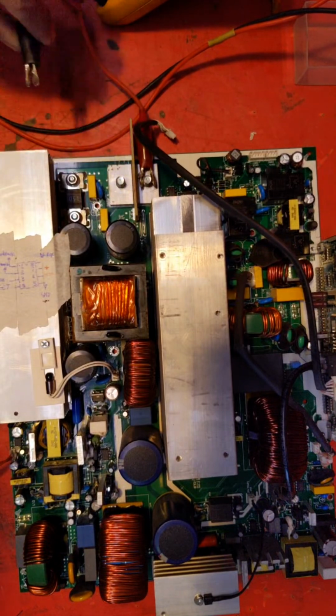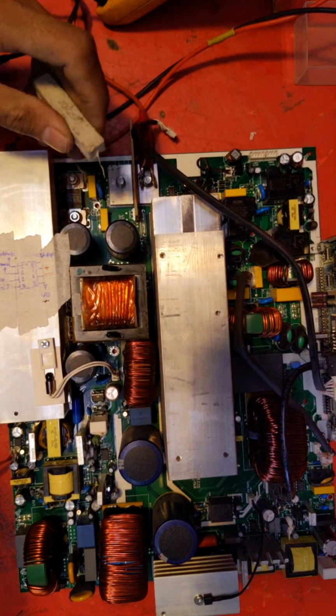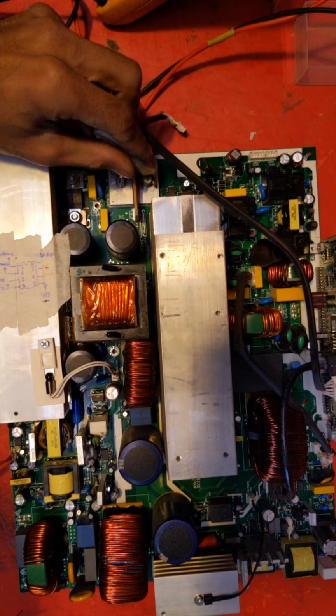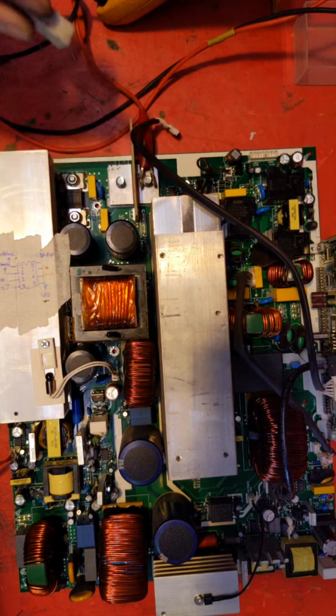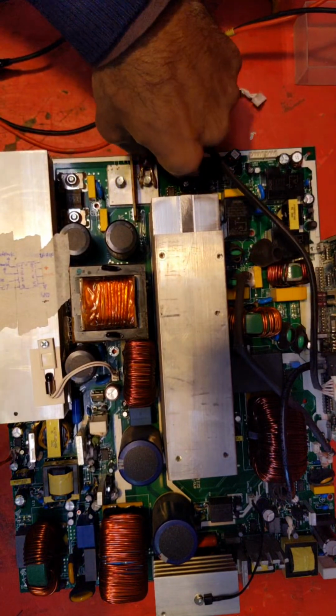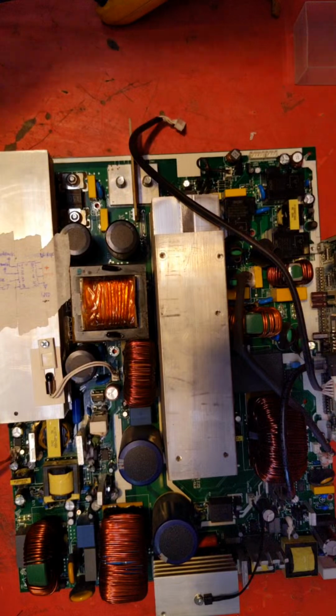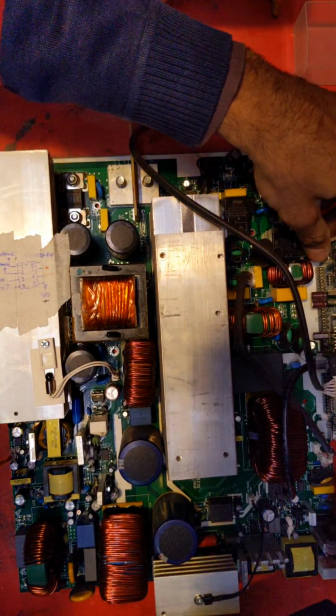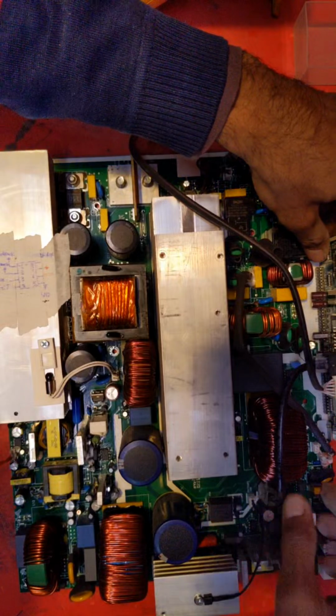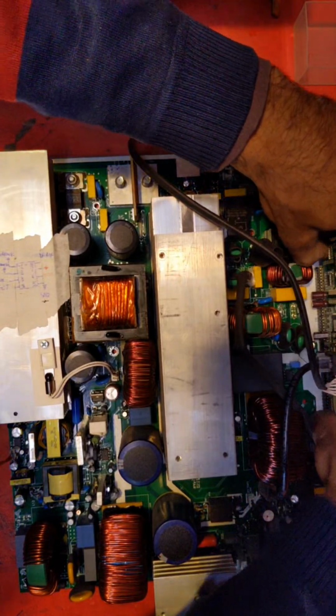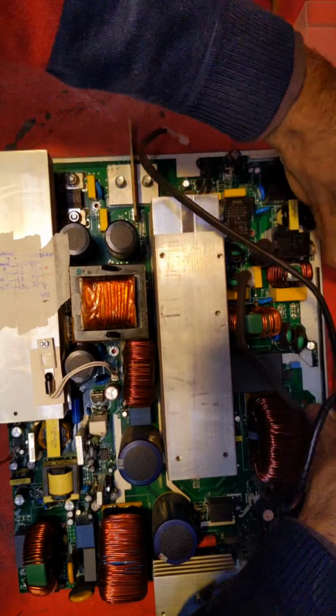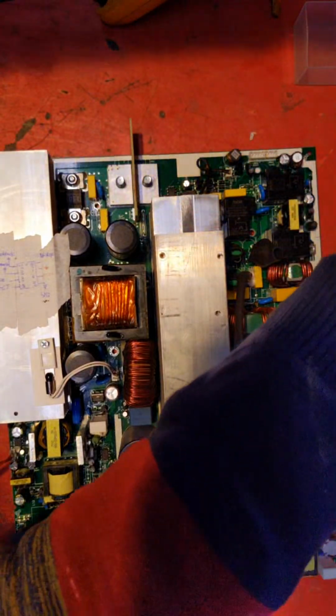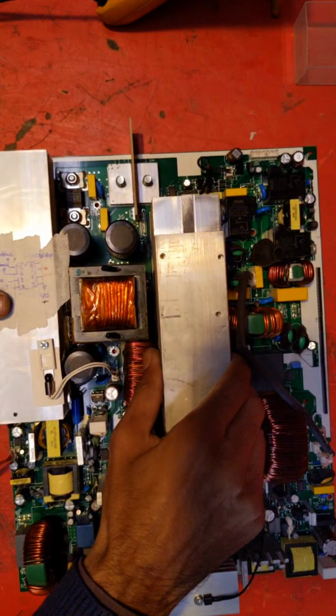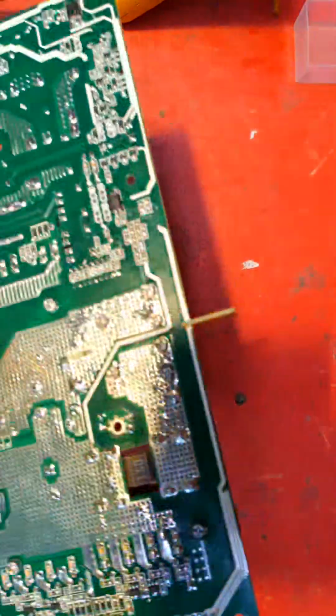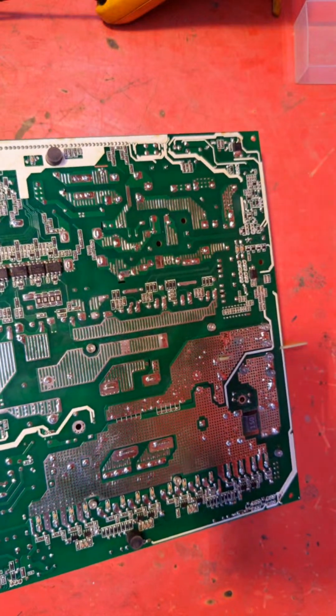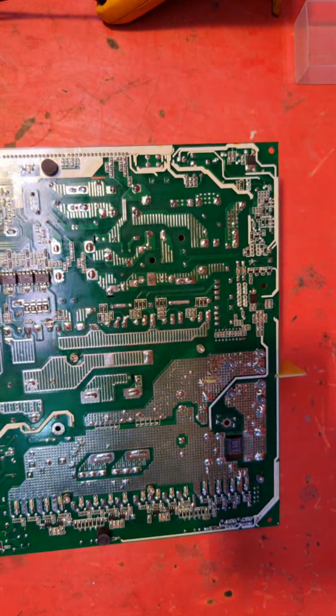First I need to do the same process to discharge the DC capacitor with some resistance in ohms. Now I need to remove the control drive card and keep it in a safe area. I removed this. Now we have two short IGBTs here, two pieces of short IGBTs.